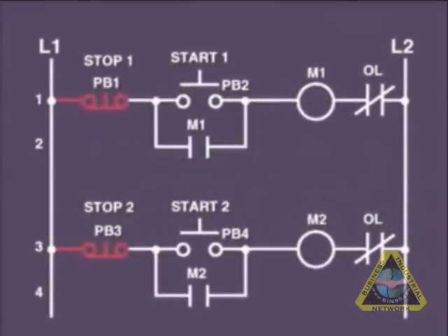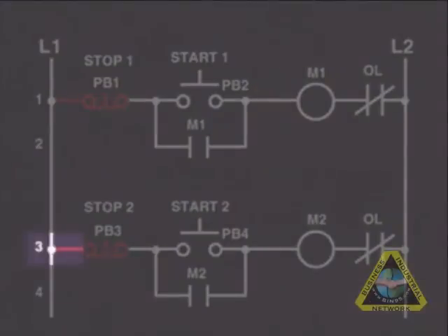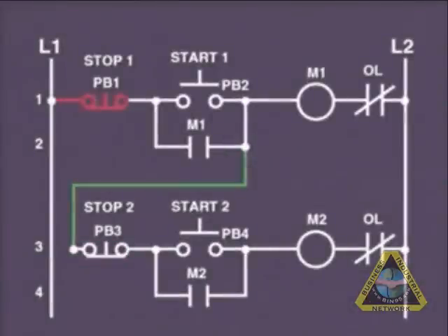We can easily accomplish this by knowing that at this point, the circuit provides information with memory that M1 is running. So, if we connect our first line of our M2 starter circuit line 3 to this point, we would get available power for M2 only if M1 is on.